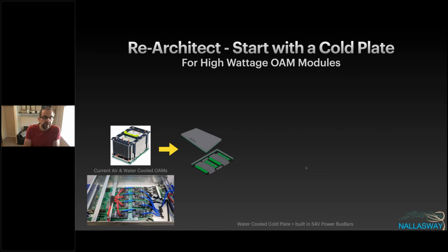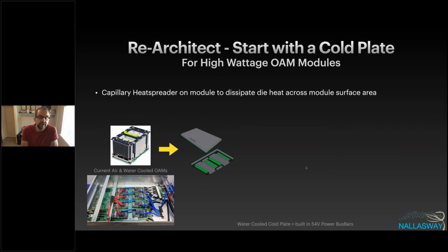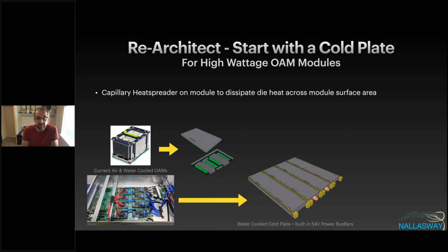But couldn't we potentially - to Philippe's point - try and normalize, if we could get a heat spreader that you'd add to your particular module, where you had a capillary heat spreader that could dissipate the core heat of the die across the entire area of the OAM module, so you have a better thermal starting point on the module. And could we, instead of putting individual cold plates, make one ginormous cold plate with one pipe in and one pipe out, so we don't have these interconnect problems with our water cooling pipes, or the rat's nest that you see on the left?